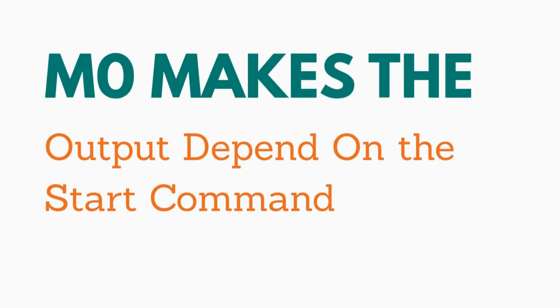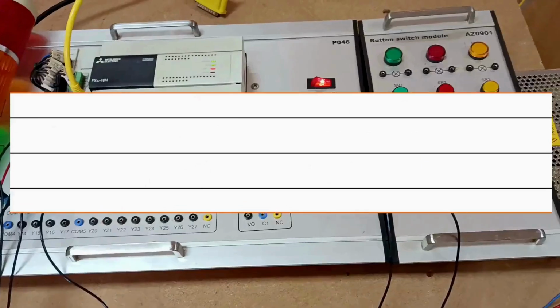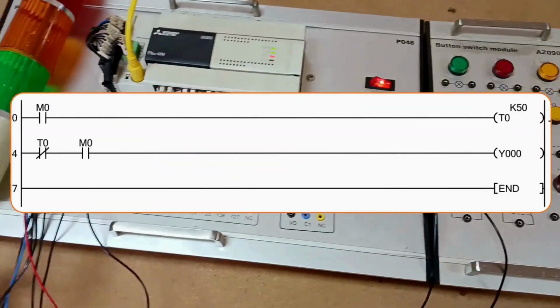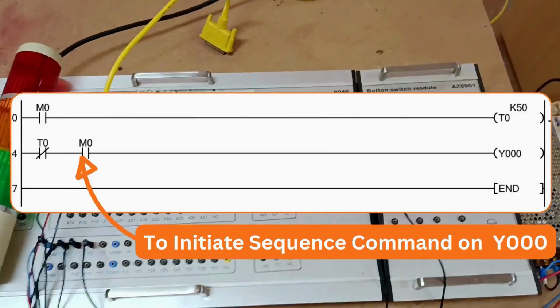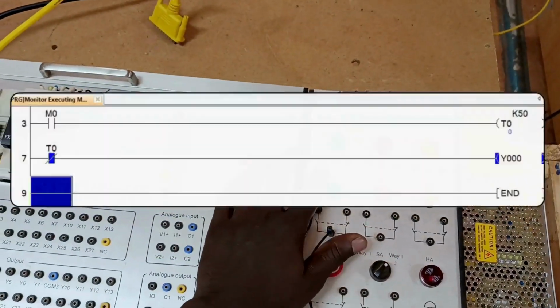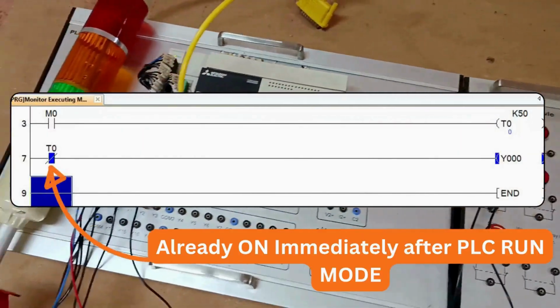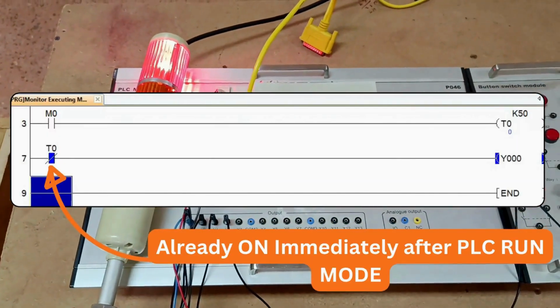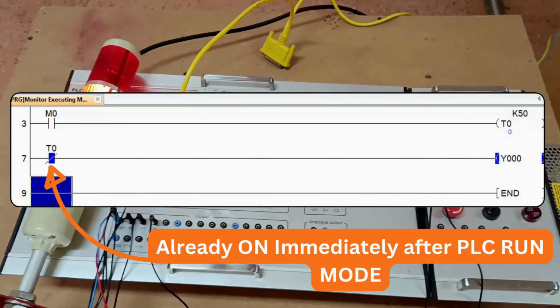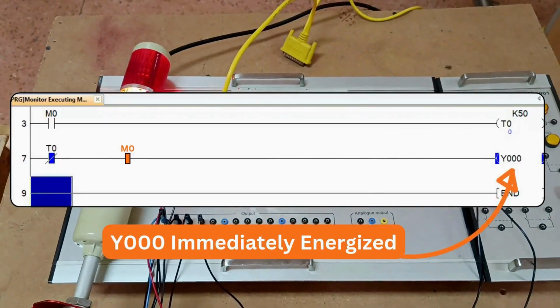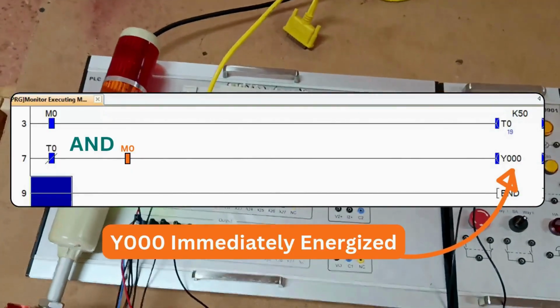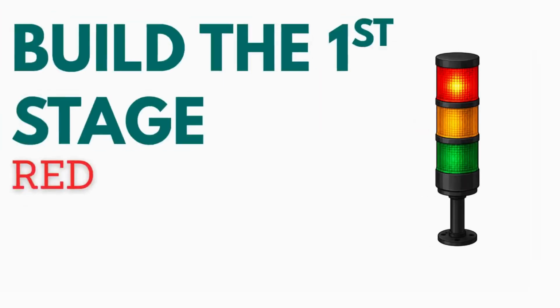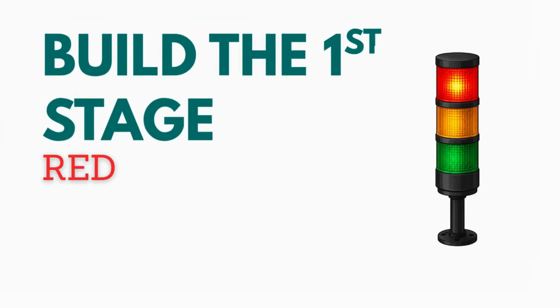We don't want the timer's normally closed contact to control the output by itself. M0 first establishes that the sequence has actually been started. The normally closed timer contact determines whether the timer stage is still active. The output is now controlled by both the sequence command and the timer state. Now let's turn this into the first stage of our actual sequence.